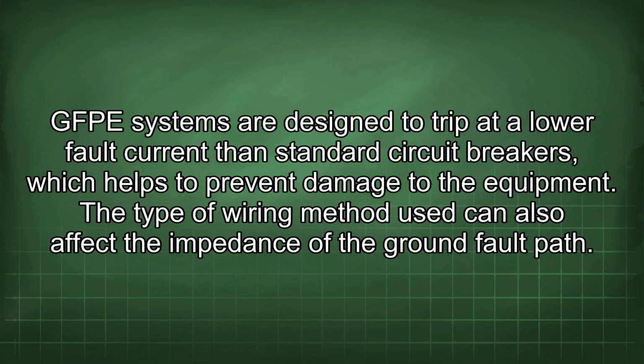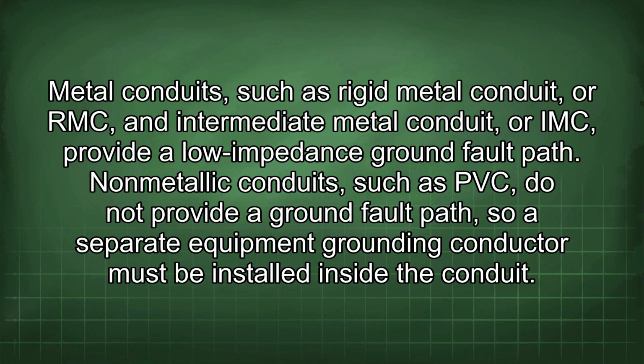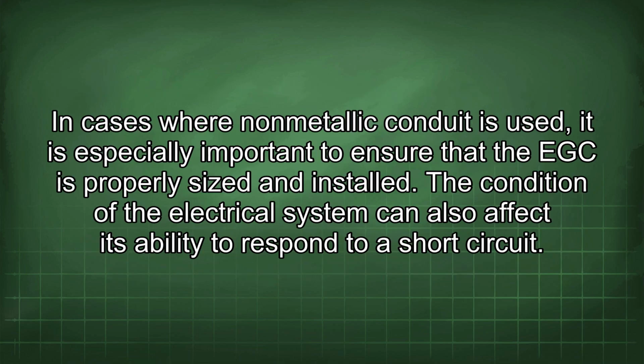The type of wiring method used can also affect the impedance of the ground fault path. Metal conduits, such as rigid metal conduit, or RMC, and intermediate metal conduit, or IMC, provide a low impedance ground fault path. Non-metallic conduits, such as PVC, do not provide a ground fault path, so a separate equipment grounding conductor must be installed inside the conduit. In cases where non-metallic conduit is used, it is especially important to ensure that the EGC is properly sized and installed. The condition of the electrical system can also affect its ability to respond to a short circuit.